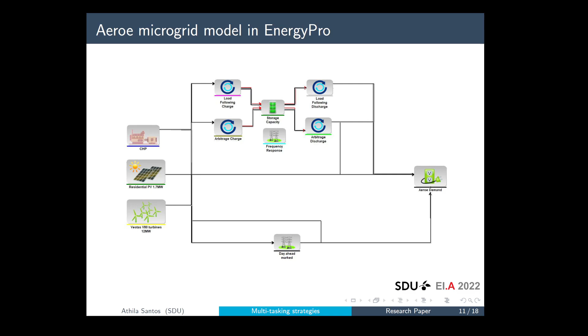As a result of the simulation, we can compare how the power capacity and storage capacity perform in the system using the net present value of this technology. We can see that 5 megawatts of capacity and 42 megawatt hours is the first selection, the initial guess for the dimensioning of the battery storage system.